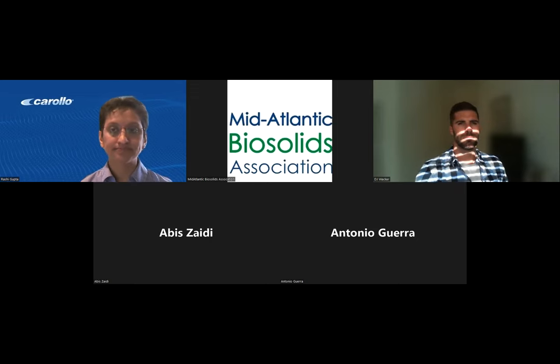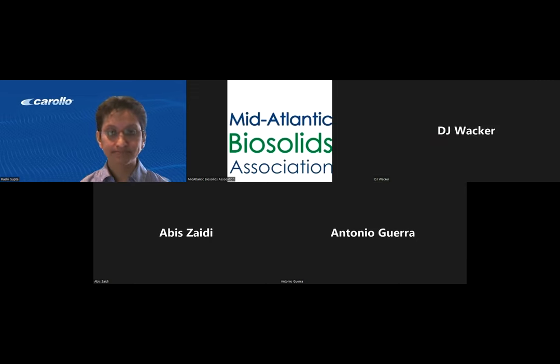Sure. So that's a very good question. And honestly, I don't have as much data as I would like to give you an intelligent answer. However, we're looking at solids concentration, whether we're talking suspended solids, volatile solids, or settling solids. We're looking at total solids in the stream. There are cases where seasonal changes, for example, will definitely affect the existing calibrations. So we can recalibrate instrumentation, but the controls remain the same. So that's the answer I've got on that question.